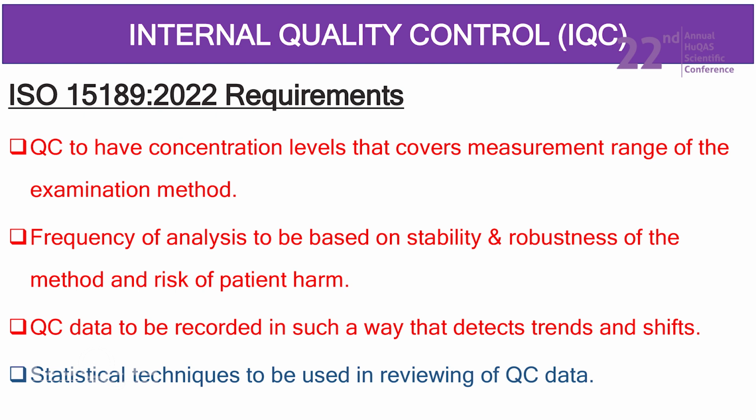The frequency should be based on the impact of this particular test. Now, when you go to most of these electrolyte analyzers, they will do their own internal calibrations maybe 3 times in a day or 4 times in a day. But when you ask how many QC results do you have for this machine, they'll only show you the IQC run that was done in the morning. So how did you verify that the other calibrations were actually correct?